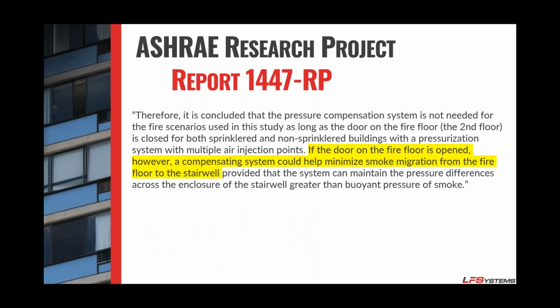And again, this was kind of discussed in an ASHRAE research project. And it's kind of funny. It says, it's concluded that the pressure compensated system is not needed for a fire scenario used in this study, as long as the door on the fire floor is closed for both sprinkled and non-sprinkled buildings. If the doors on the fire floor is opened, however, compensating system would help minimize smoke migration from the fire floor to the stairwell. Again, change the word stairwell to hoistway, same thing. So basically, as long as you don't open the door on a fire floor, you're fine.